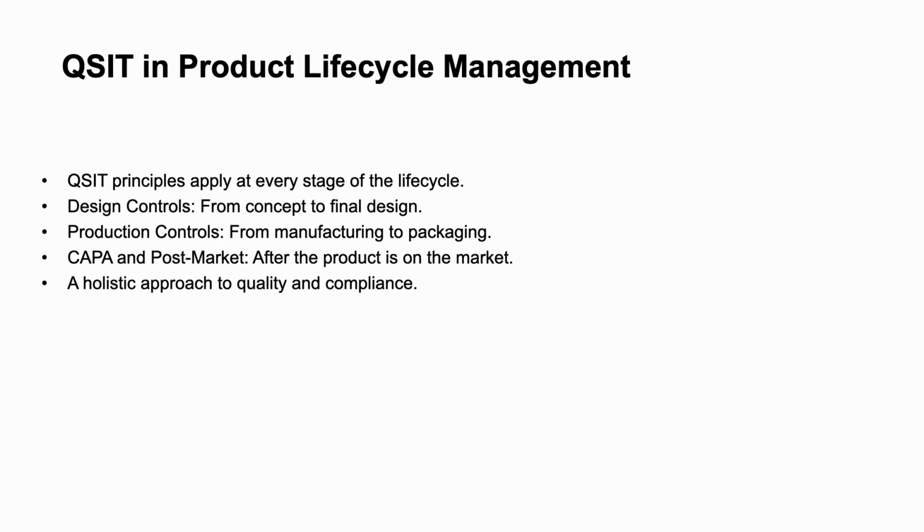QSIT is not a one-time event. Its principles apply throughout a medical device's entire life cycle, from the moment a device is just an idea on paper to the years it spends on the market. QSIT provides a framework for quality oversight. The design controls subsystem governs the early stages, ensuring that the device's design is safe and effective.